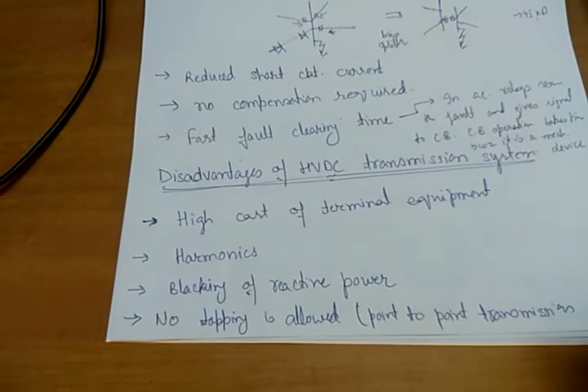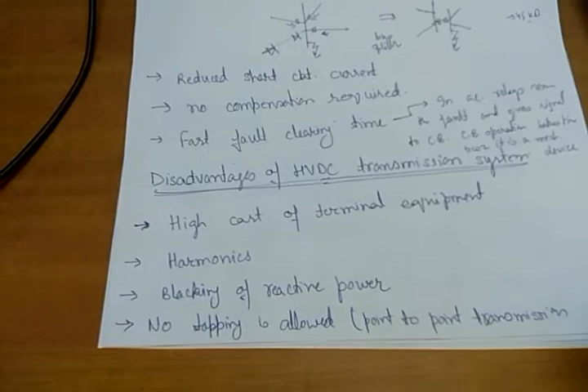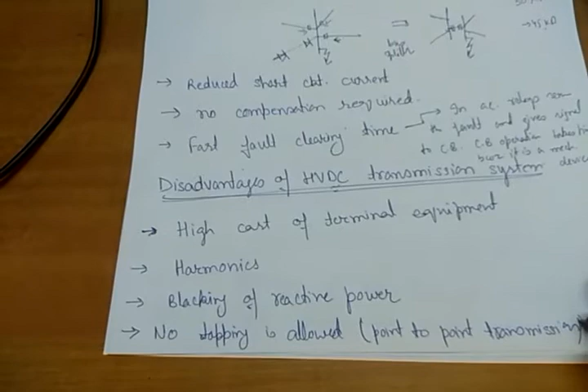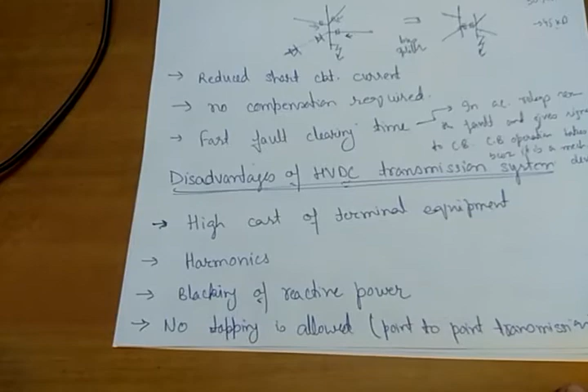No tapping is allowed. No tapping is allowed means we are designing the system for a constant current mode of operation. So point to point transmission is possible only, and tapping in between is not allowed. If you want to tap the current in between, then you have to use another terminal.